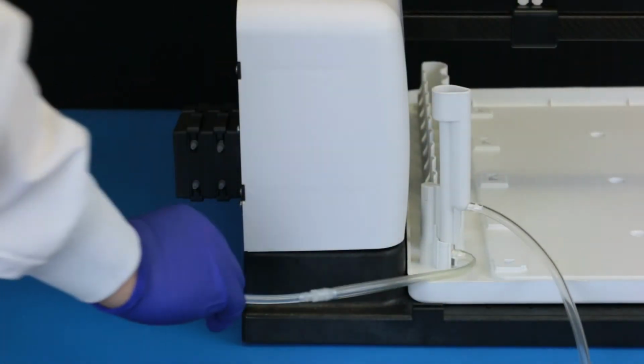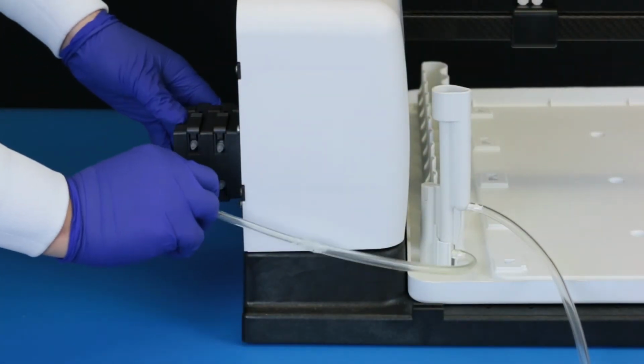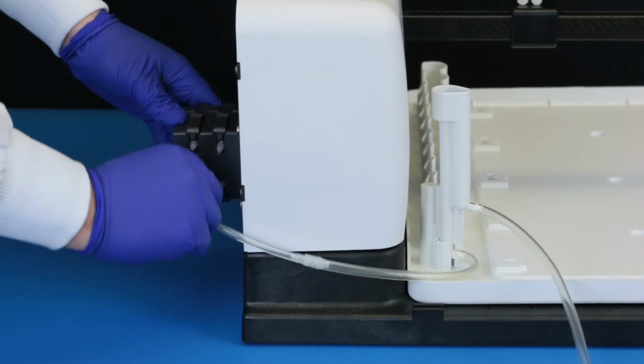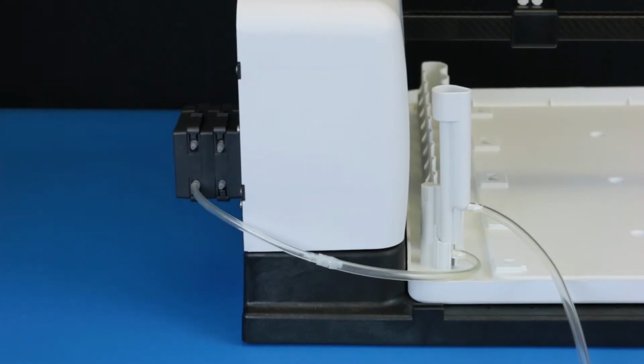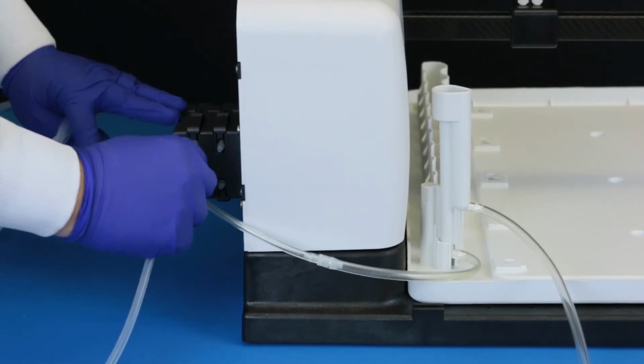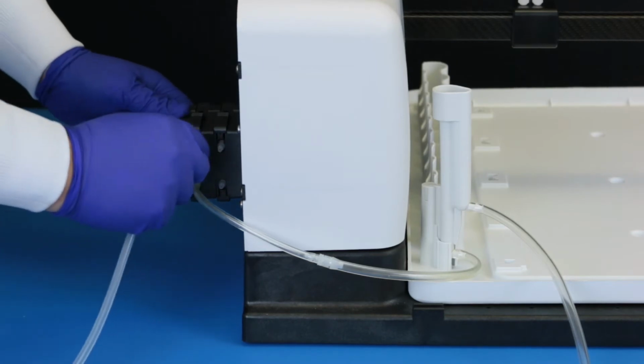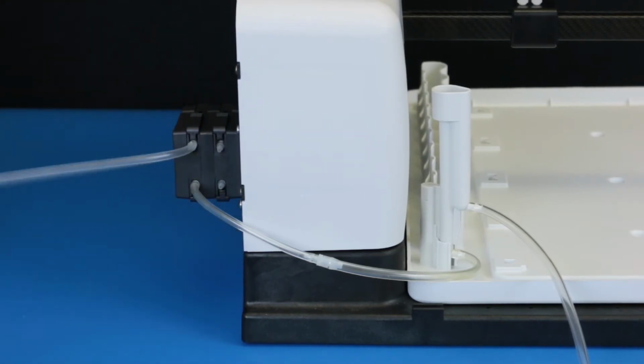Connect the inlet tube to the bottom fitting of pump channel 2. This is the channel farthest from the back of the autosampler. Connect the tube from the bottle of rinse solution to the fitting at the top of this channel.